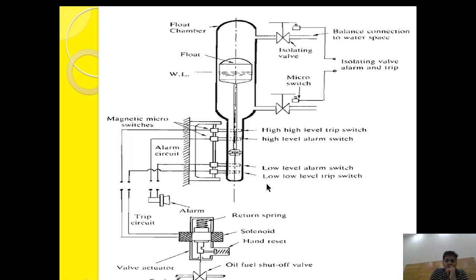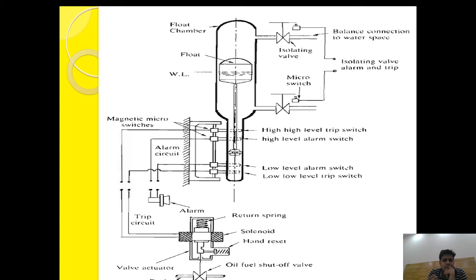The boiler water level needs to be maintained properly. Sometimes due to priming, gas formation, or a fracture in the line, a low water level alarm can occur, and necessary action must be taken. When the magnet is moving to any of its switch positions, the corresponding micro switch completes the alarm circuit.